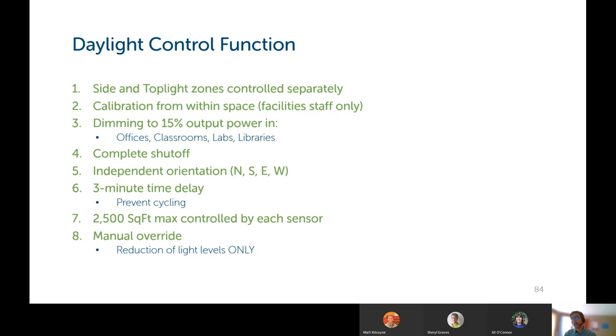A 3-minute time delay for the daylight levels so that you prevent cycling. Each daylight sensor can control a maximum of 2,500 square feet. And you can have a manual override to dim switches, or only to reduce light levels in those spaces. You can't have manual override to increase it in daylight zones.